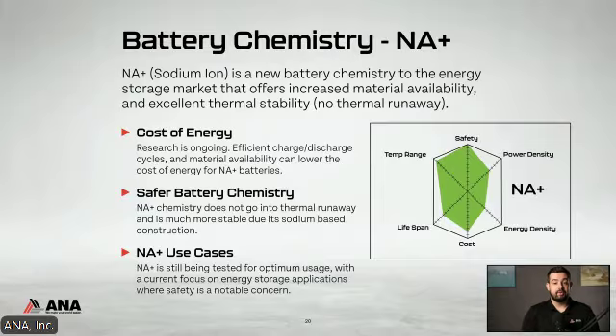Due to the inherent nature of the chemistry, you cannot induce thermal runaway at all. It won't catch fire. However, it does off-vent flammable or toxic gases. So there is a risk with Na+, as with every other battery. But typical use cases: it is up and coming, but as of right now, it is used for backup or UPS systems, and it's starting to replace 12-volt batteries that you would see in, let's say, a generator or a golf cart. It's starting to replace those lead acid batteries for now.